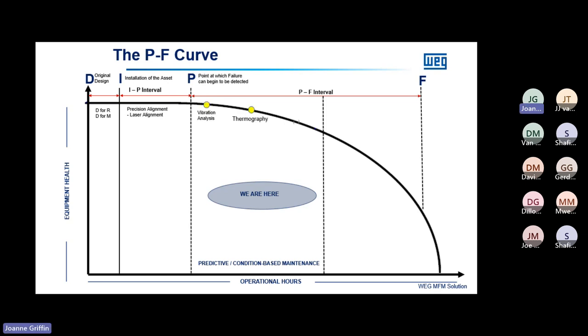Some of the activities we do during this condition-based monitoring window include vibration analysis, thermography, and ultrasonic spike energy measurement. This list is not exhaustive — some also do oil analysis and so forth. The point is that this window is your opportunity to act on the machine before you reach reactive maintenance.